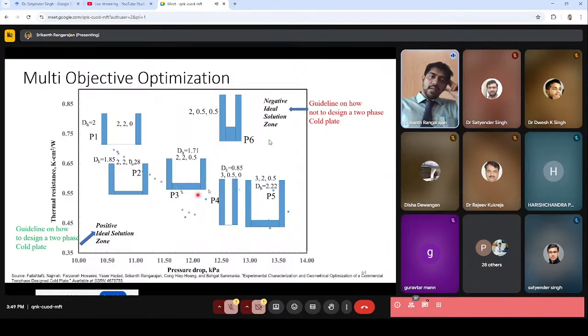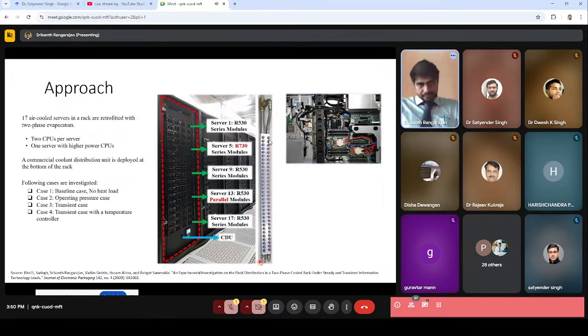So we developed guidelines on how two-phase cold plate designs have to be made by making a lot of inferences from this. Not only that, we also learned how not to design a cold plate for two-phase, because by making an inverse of this problem, instead of saying that I want to design a good cold plate, if I pose it as if I want to design a bad cold plate, you can still get some designs that are very bad for both the thermal resistance and pressure drop, which can be invaluable data on how not to design a cold plate.